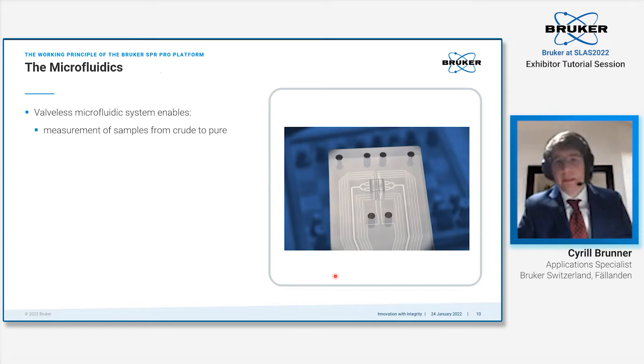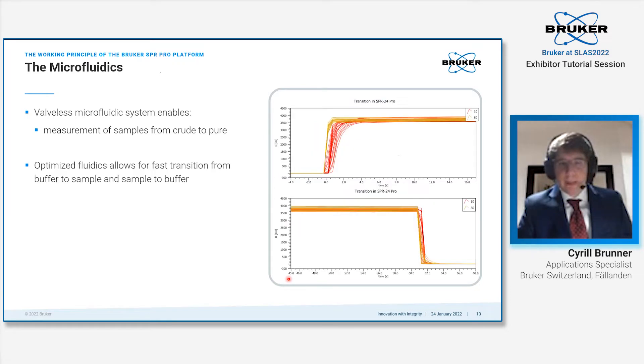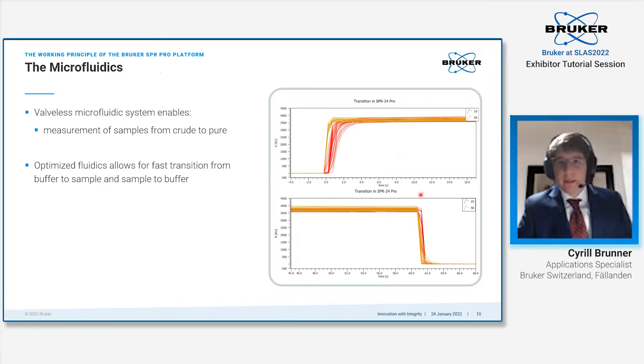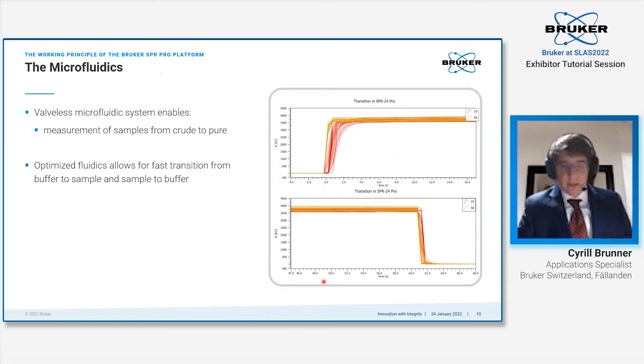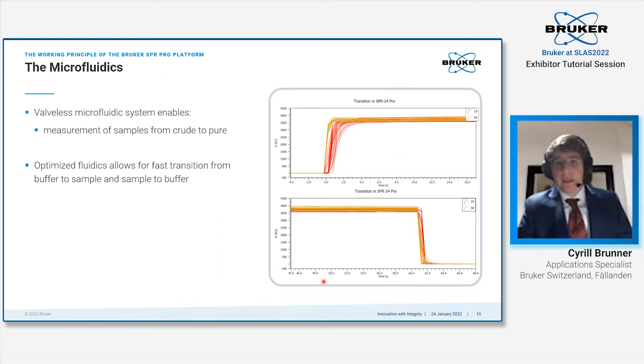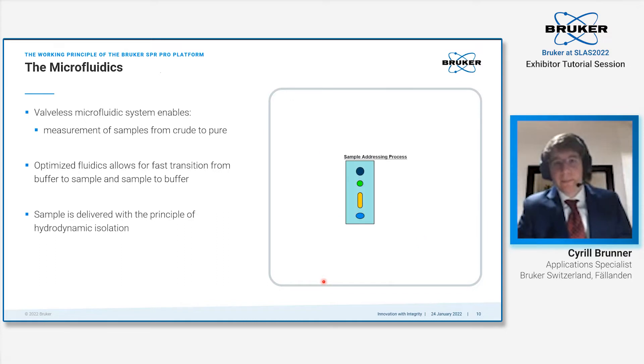The microfluidics of the system is made up in such a way that we are valveless, meaning you can easily use crude samples. There are no parts which typically fail after some shorter time. The fluidics has been optimized for fast transition from buffer to sample as well as back from sample to buffer, giving you the possibility to easily analyze compounds with fast association and dissociation rates.